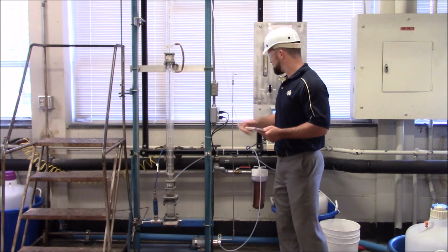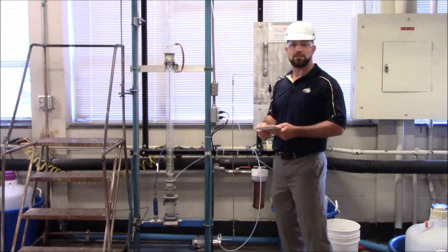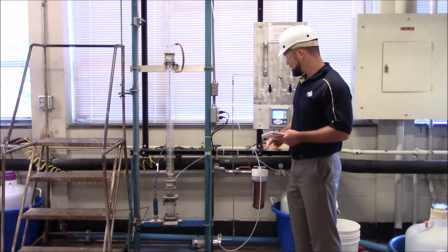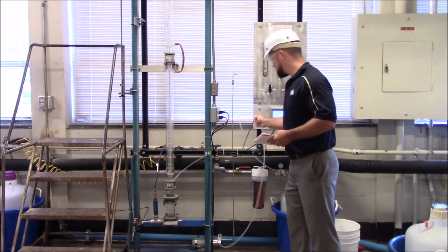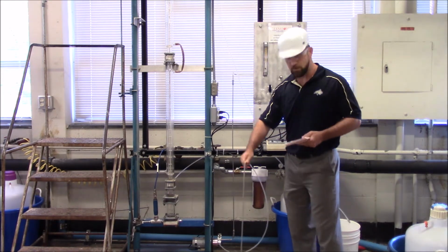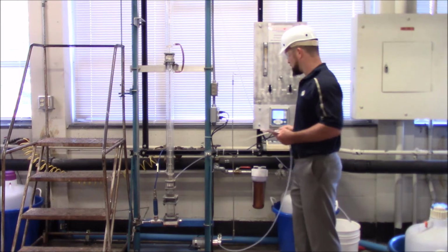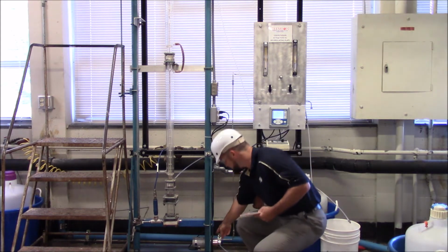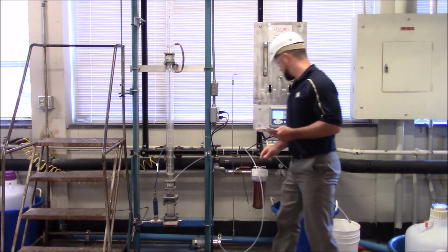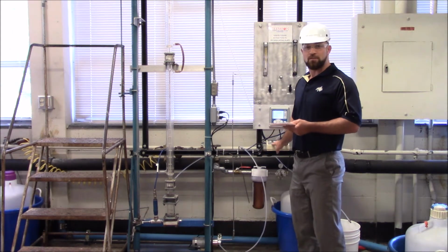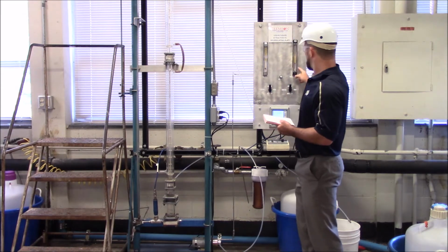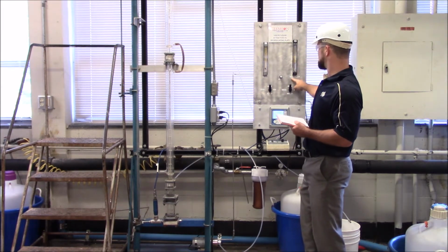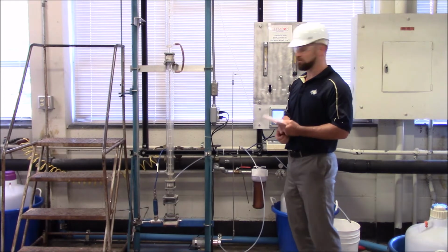Okay, but let me talk a little bit about how we control the feed to the system. We feed the MIBK to the system, so we have a feed line which will go into our carboy feed, which I'll discuss in a few minutes. The feed of the solution is controlled using a pump down here. The controls to the pump are shown on this control panel here. We can see what the flow rate is using this flow meter, labeled acetic acid MIBK mixture.